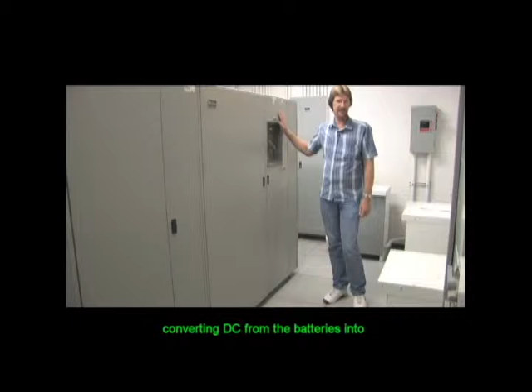So this is the UPS. It supplies power to the servers, the west half of the call center, and the emergency lighting in the event of a power outage. One thing I want to stress is that the power doesn't actually switch back and forth to the servers. Power actually feeds this all the time, charges the batteries, runs the inverter, and that power is what's sent to the servers and everything else. So if the power drops out, there isn't a switching action going on. We're just charging the batteries all the time.